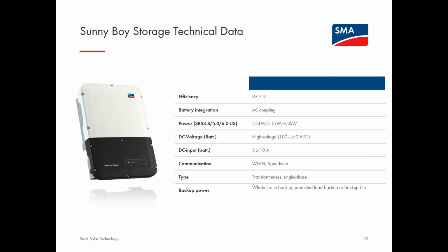We offer it in 3 different power classes. These are the nameplate power ratings of 3.8 kilowatts, which is perfect for landing on a 20 amp backfeed breaker. There's a 5 kilowatt and a 6 kilowatt version available. Because we've repurposed the topology from the SunnyBoy, you may know the SunnyBoy PV inverter has up to 3 maximum power point tracking inputs. We've repurposed those input channels for the SunnyBoy Storage to allow them to connect to a battery and to charge and discharge a battery. In doing so, we are able to mix and match different batteries of different voltages. So we have a very wide operating range on the DC input side between 100 and 550 volts.